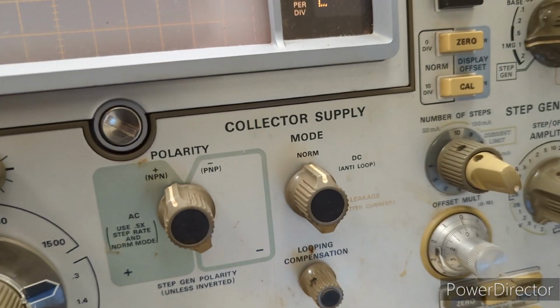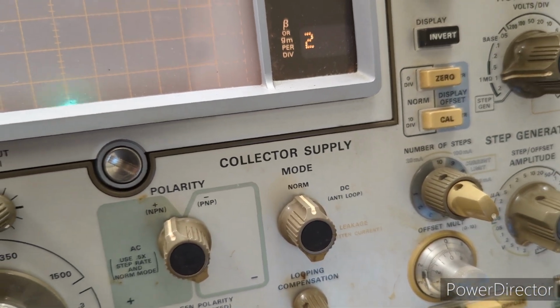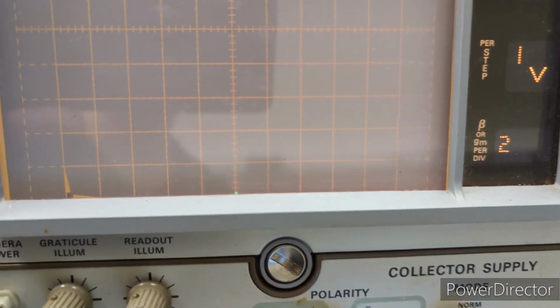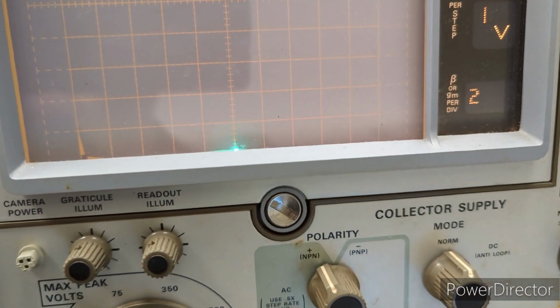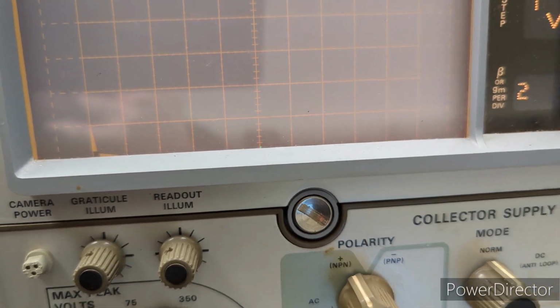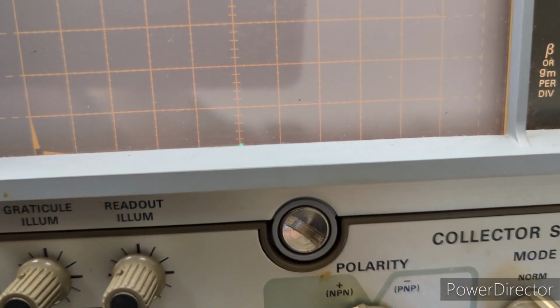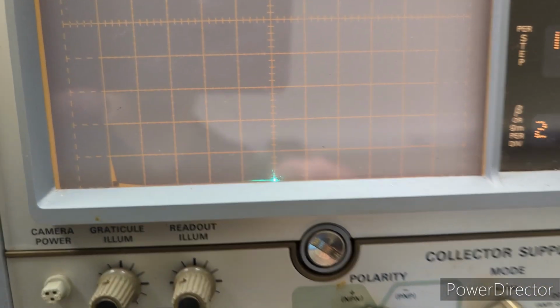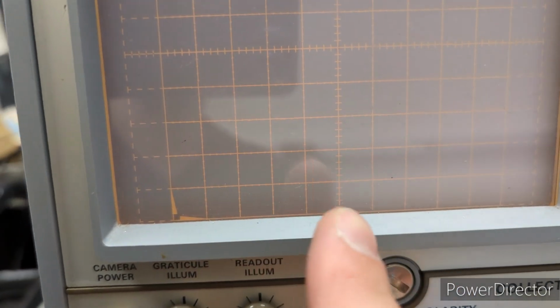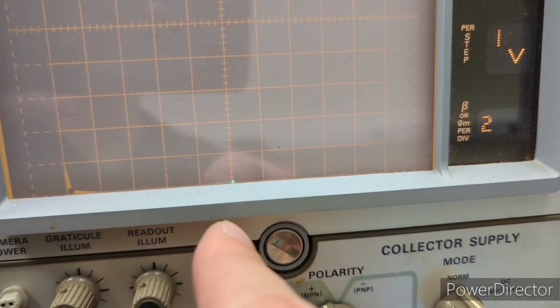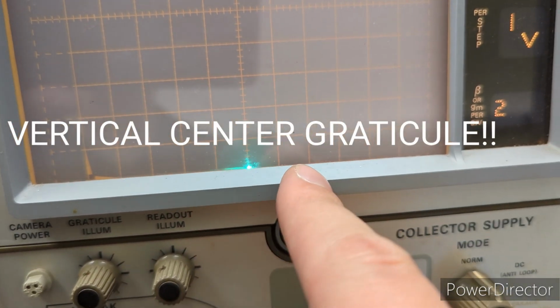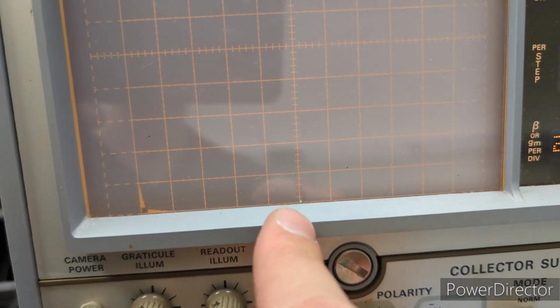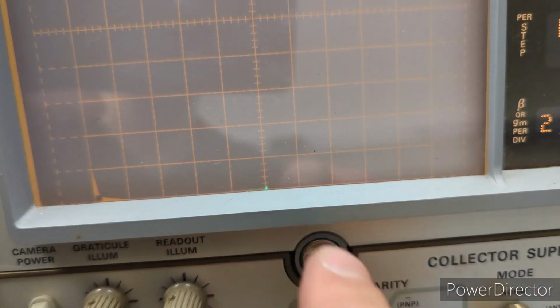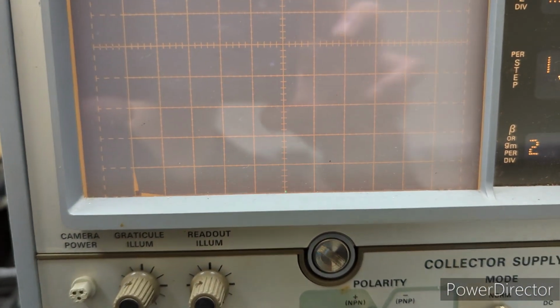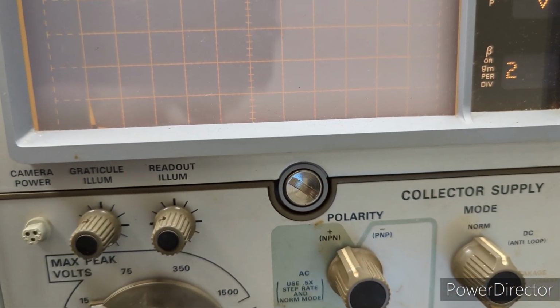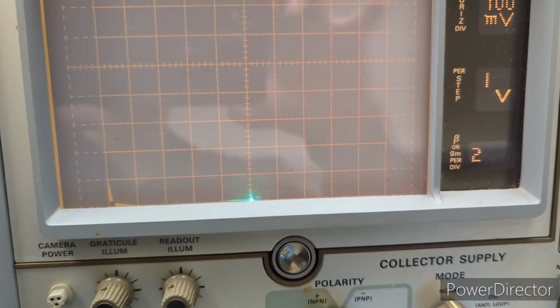Okay, so I just finished up the step amplifier gain, and actually all of the settings within this step were okay. They had a quote-unquote wide range. It could be plus or minus 2 divisions around the center CRT graticle, so that's where the trace should be. It could be somewhere within 2 divisions that way or 2 divisions that way. I still made an adjustment anyway for each to get it right on the center, but everything was looking good in that respect. And so now we can move on to the current balance, see what happens with that.